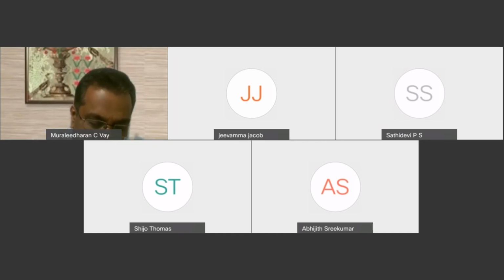Extremely good mechanical valve designs may not work well in this type of environment, mainly because the blood damage during the functioning of the device is one major factor in the success of the device in the specific location. So we should be able to control the blood damage effectively. Otherwise, this blood damage will generate a cascade of events, what we call platelet aggregation and platelet attachment, and that will be detrimental to the device. So it's not just the mechanical wear and tear. There is more to do with the biological system also.